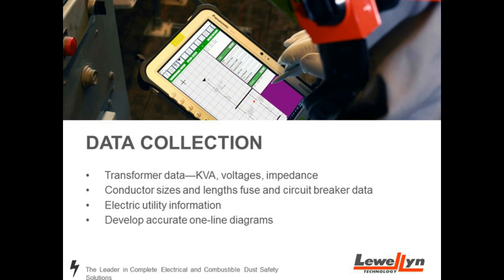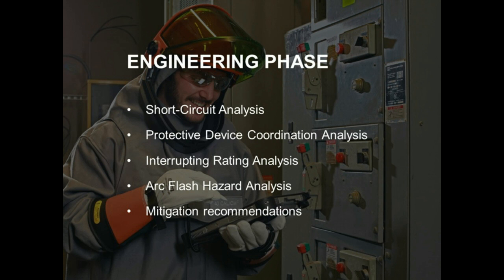The second part I talked about is the engineering. There's a series of studies done to arrive at the main goal. There's a short circuit analysis of how much is coming, a coordination analysis that determines the order of how things function in the building - the fuses and breakers, and how quickly they can interrupt the fault that's coming. And then there's obviously a rating for the arc flash hazard.